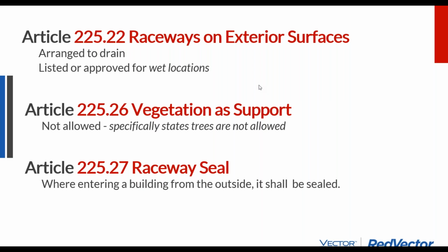Raceways on exterior surfaces need to be arranged to drain. That means making a weird loop going into the underside of the equipment rather than into the top or the side, which is often the only manufacturer-supported way of entering equipment on exterior surfaces. So sometimes aesthetics can get in the way when you try to make something look good. If you aren't arranging it to drain, you can get water into the box, and good looks are not as important as safety in this issue. Vegetation support: electric code has come on to say no, you can't just use regular trees as support for your power lines or crazy solar arrays.